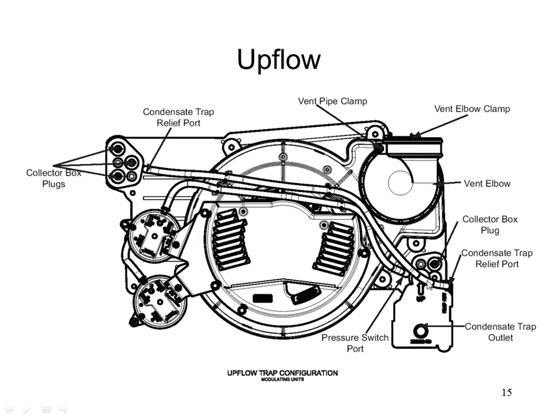All I really have to do in that situation is, on the left side here where those three plugs are, I take those three little plugs out, I undo two screws on the condensate trap, and I move the condensate trap over here where these plugs are, and I move the plugs over where the trap is. So I just flip-flop those two guys, so that way the condensate trap is always on the bottom.